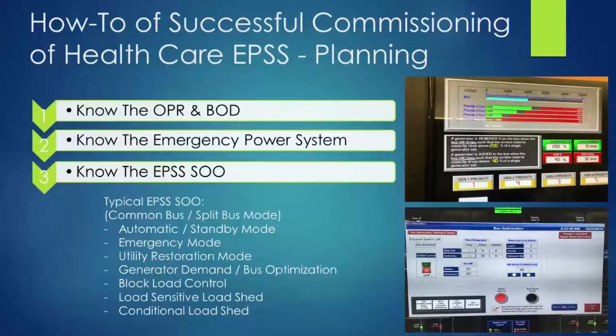A typical emergency power system sequence of operations can either have a common bus or a split bus mode. One thing to note: if you have a split bus configuration, you're going to have two tests — a common bus mode test, and a split bus mode operation test. So that's something to keep in mind.